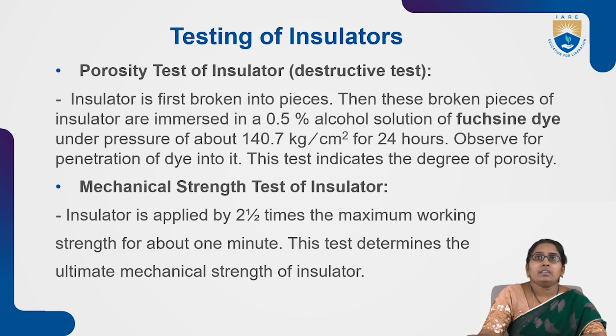They apply that for 1 minute, and then the insulator should withstand it. So this test indicates the ultimate mechanical strength of the insulator.